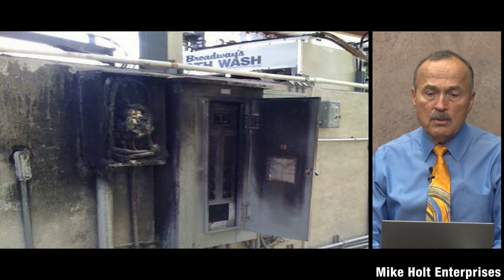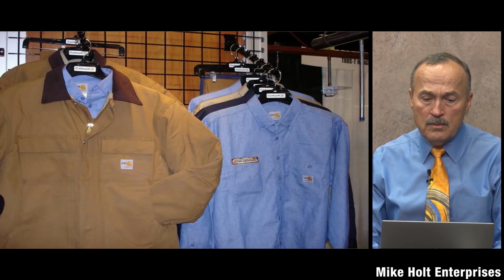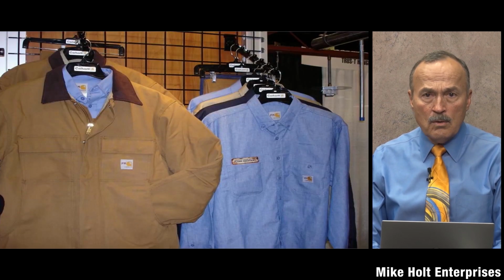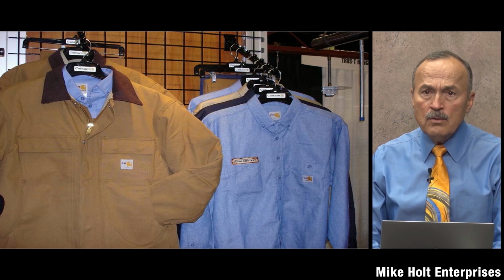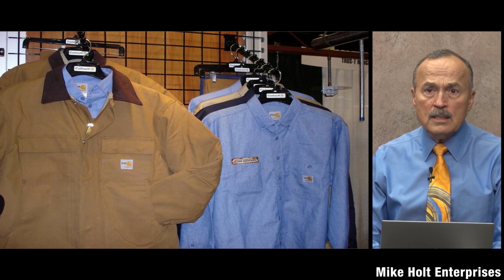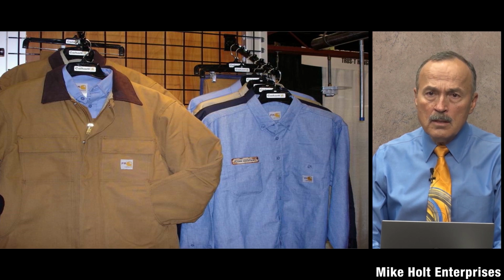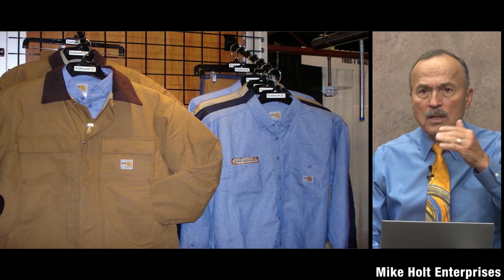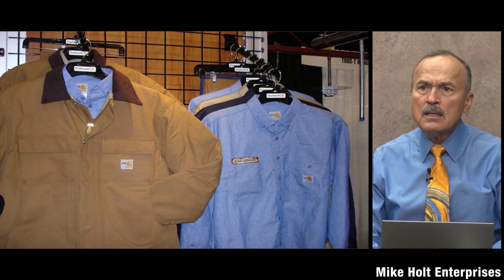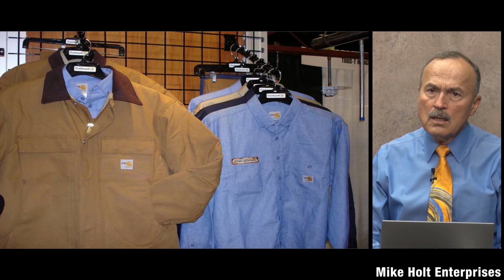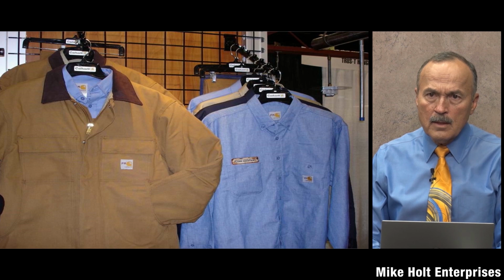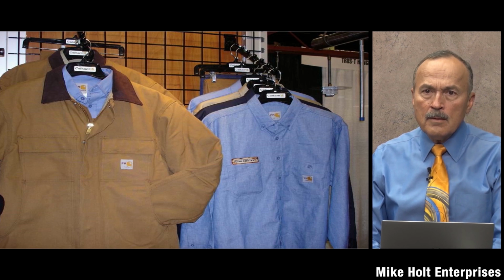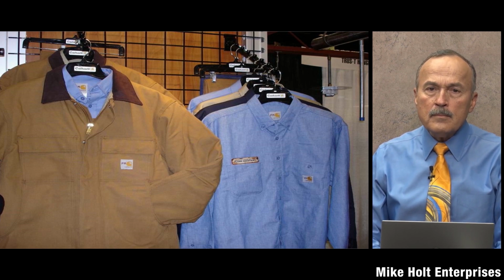Here's another example to look at - that's a big deal. So here's the clothing, Ryan, you go and look at the label, it says 5.6. I don't know clothing, so would 5.6 require something like a 12? No, 5.6, maybe an 8 - you could buy clothing rated higher than that, but an 8 cal clothing. The standards are 4, 8, 25, and 40, but there's stuff in between you could buy as a layering system that could be 12 or 16 or 22, depending on what you want.